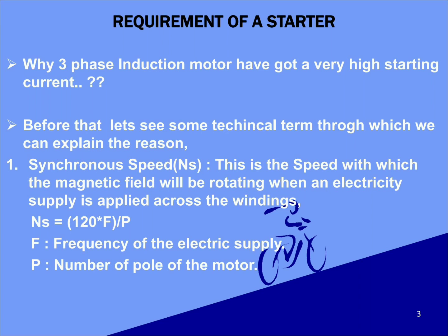Now let's see the requirement of a starter. Why does a three-phase induction motor have a very high starting current? We all have heard that induction motors have very high starting current, and to explain that, let's see some of the technical terms related to that. Synchronous speed. This is the speed with which the magnetic field will be rotating when an electrical supply is applied across the windings. Given by the formula Ns is equal to 120 F by P, where F is the frequency and P is the number of poles.